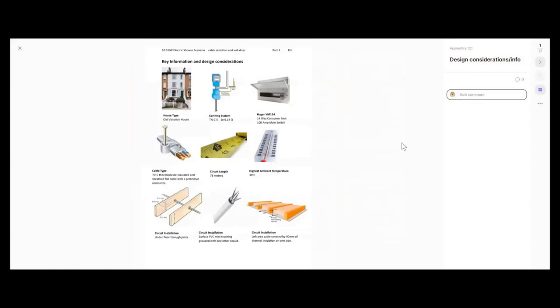What I've tried to do — which I used to do back in my teaching days — is to visualize some of those important items and considerations we need to make from the spec. The house type we know is an old Victorian. Earthing system: TN-CS, PME. Picture of the DB that's installed — it's a Hager VML14. Cable type is flat twin. Circuit length is 78 metres. Highest ambient temperature is 30 degrees C.